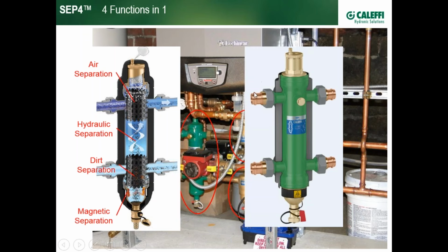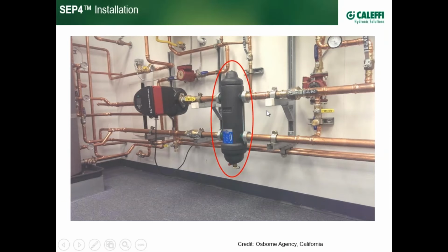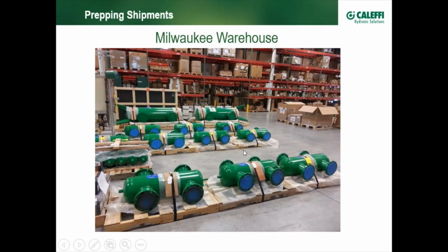By the way, notice the press connections recently introduced in 2016. And let's take a look at one installed, which looks like this. Doesn't quite look the same because it has its Caleffi furnished insulation jacket added. On all Caleffi SEP4s, as well as hydraulic separators with union connections of 2-inch and below, insulation jackets are standard. Lots of separators produced by Caleffi going out the door one day. You can see here in the Milwaukee warehouse some of the separator products.